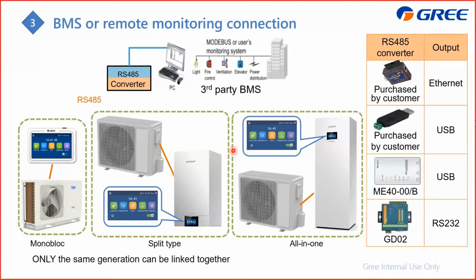And the last part is if you would like to control the VERSATI with a computer, it is also available. From this controller, there are two terminals. One is to connect with either the outdoor unit or the indoor unit, and the other output is the RS485. And also you can combine these three together, it is also okay, just like this. After you combine it, you can connect with an RS485 converter.